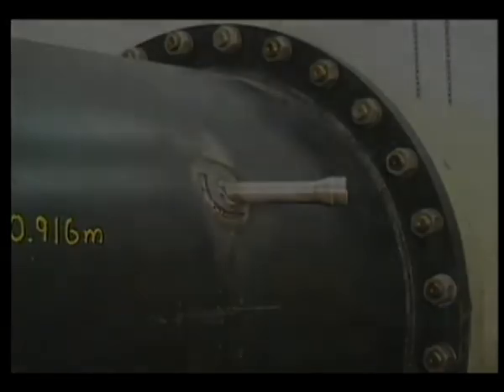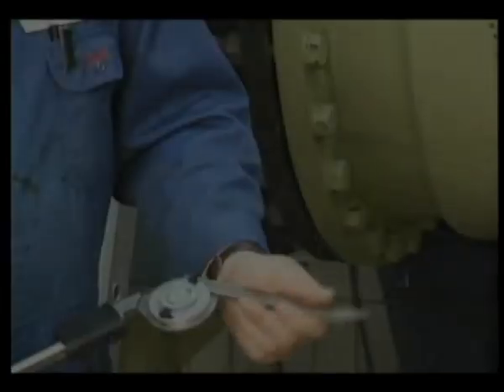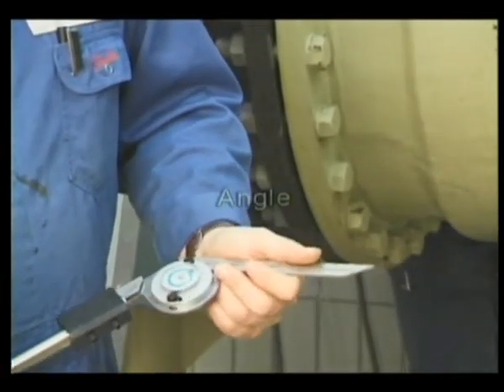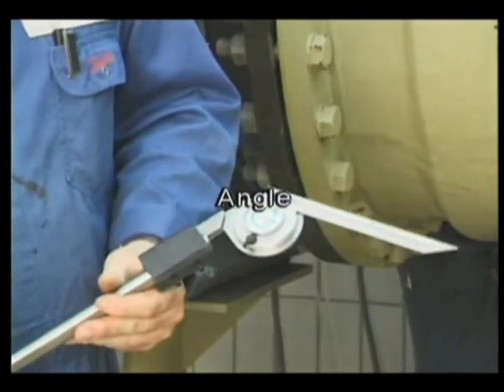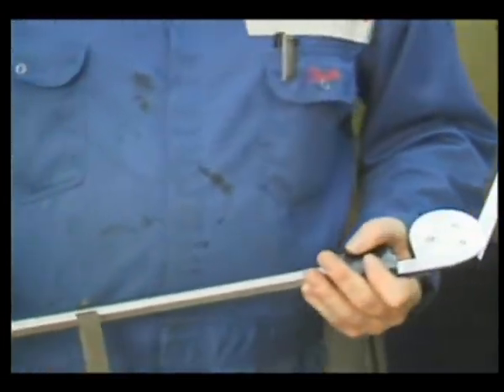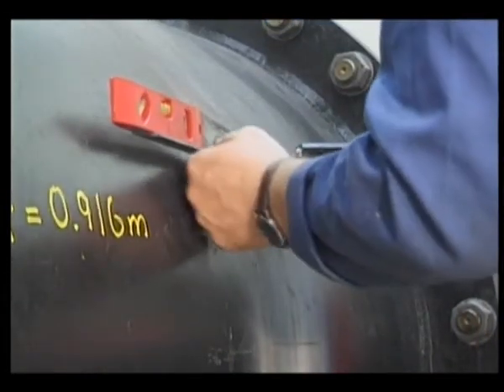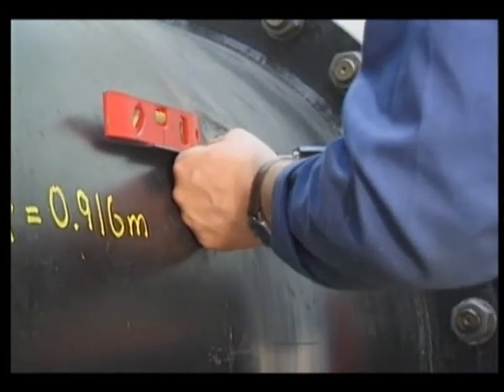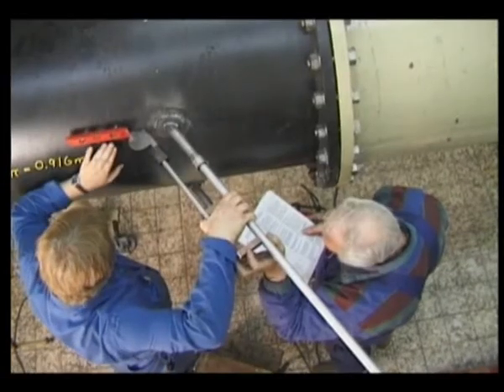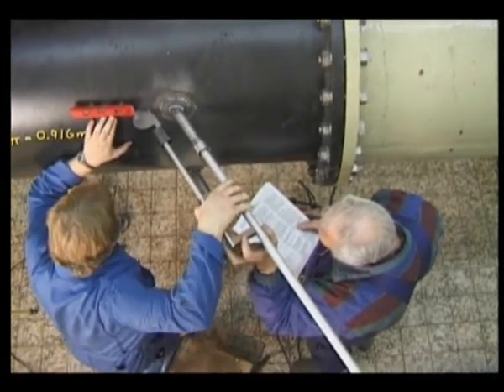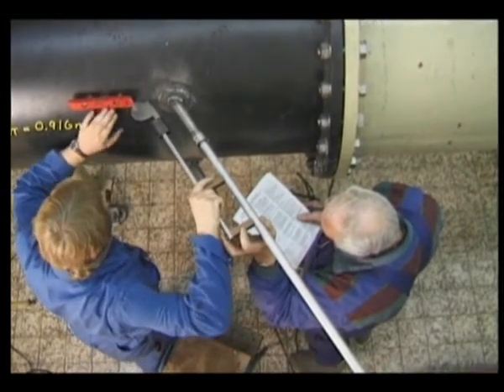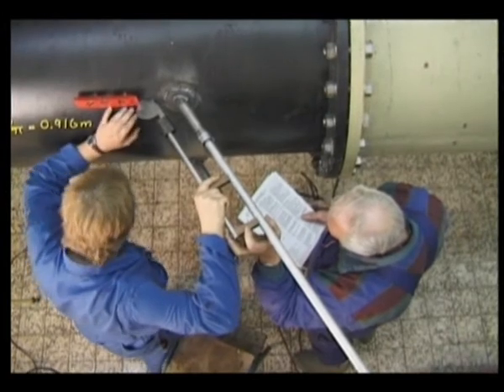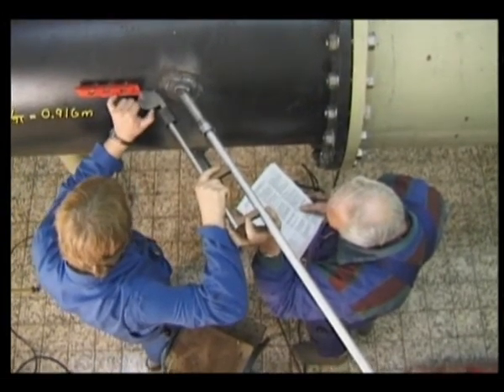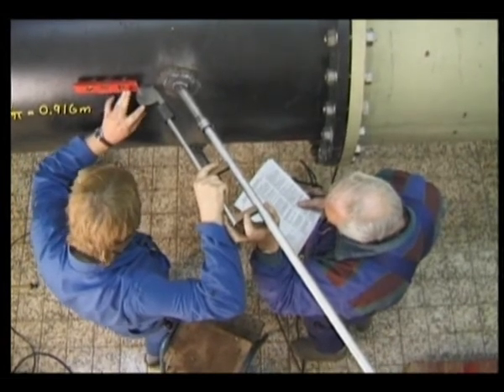When it's been mounted, the next step's to measure the new sensor. The angle of the soundtrack in relation to the pipe is measured with an angle meter as shown here. A small level meter can be applied to get the angle meter in the same plane as the pipe. It's important that the angle reading's accurate, as the track angle has a great influence on the measuring accuracy. The measurements read must be entered in a measurement report, which can be found in the manual.